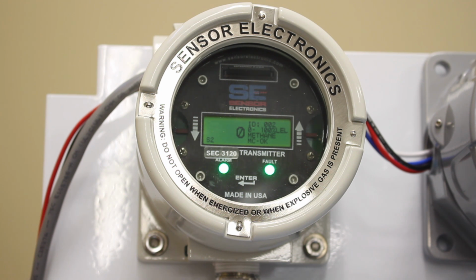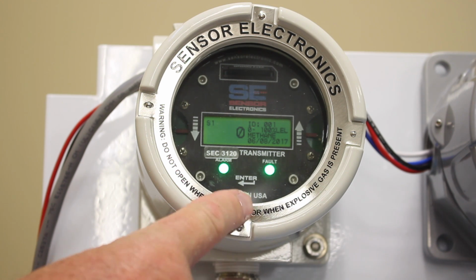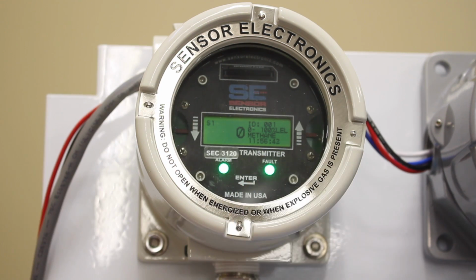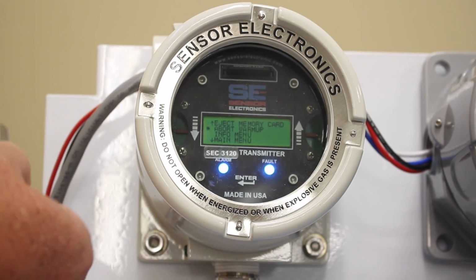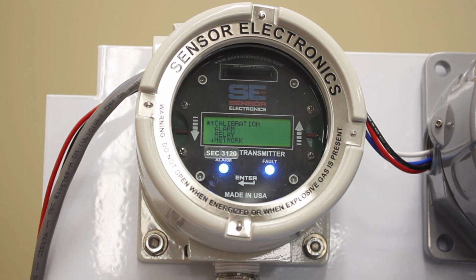To enter the calibration mode, use a magnet, and we have an enter, a down arrow, and an up arrow to navigate through the menu structure. So first we'll go into enter, and then we'll arrow down to main menu, and the cursor moves down. You select enter.